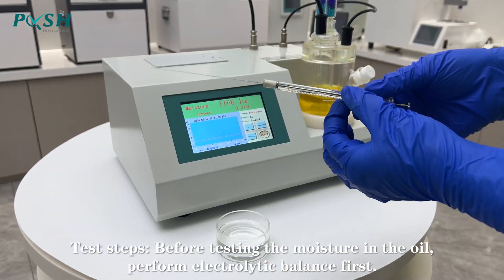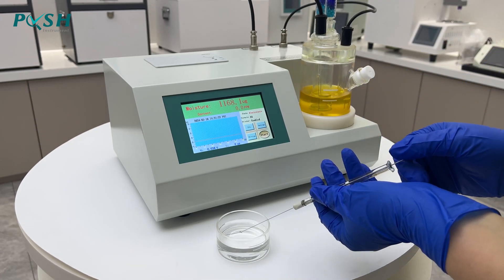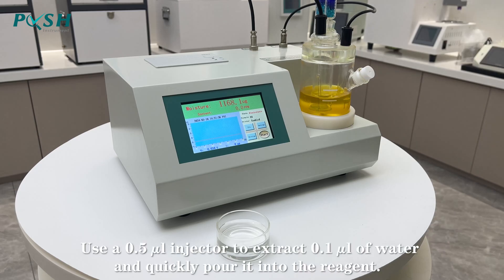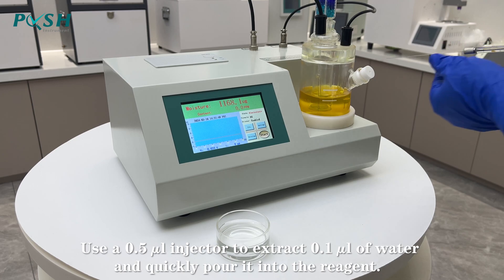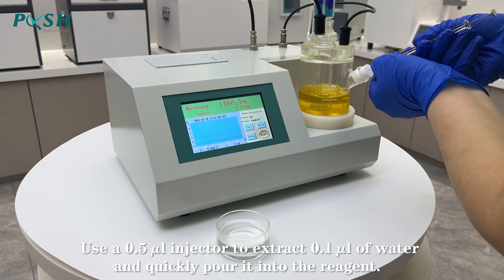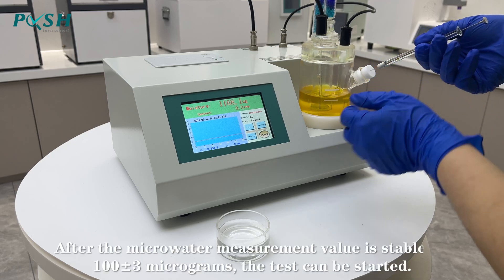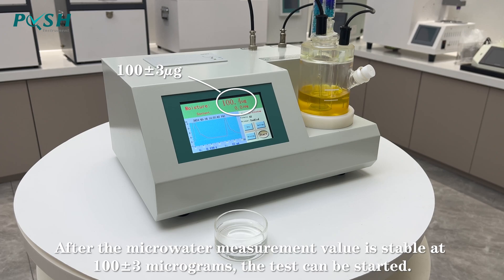Test steps before testing the moisture in the oil: perform electrolytic balance first. Use the 0.5 µL injector to extract 0.1 µL of water and quickly pour it into the reagent. After the µW measurement value is stable at 100 ± 3 µg, the test can be started.